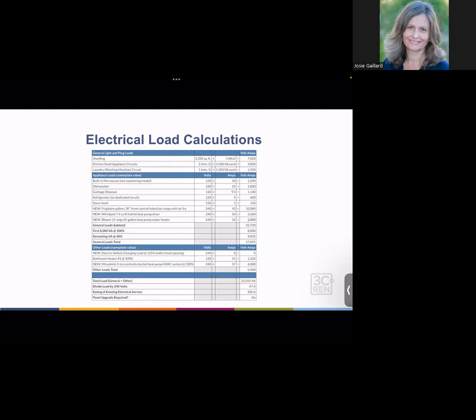For example, the range is included in the 0.4 coincidence factor bucket. One reason the code may say that's okay is because your cooking range, usually you're probably using 1 or 2 burners. It's very rare for most people to be using all 4 burners at the very highest heat and your oven at the very highest heat. So the code is assuming that generally when that appliance gets used, it's going to be used at a much lower load than its max load.